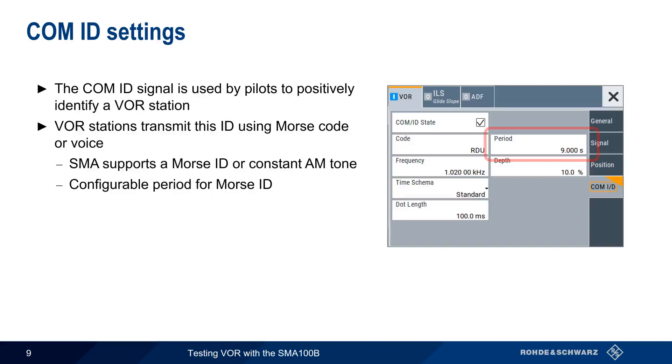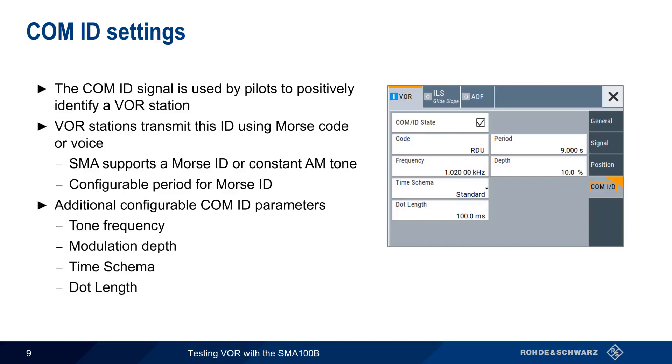The period or interval between the IDs can be defined, as well as additional ID parameters such as the frequency of this tone, the modulation depth, the time scheme, and the dot length used in producing the Morse ID. These last two parameters control the lengths and timing of the dots and dashes themselves.